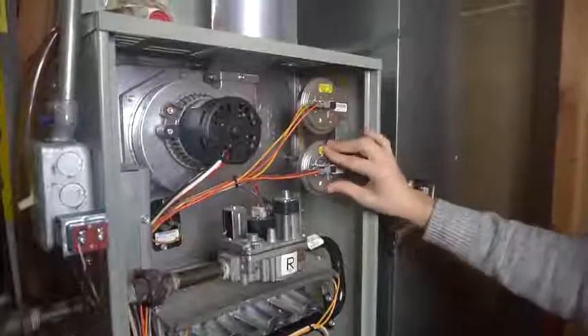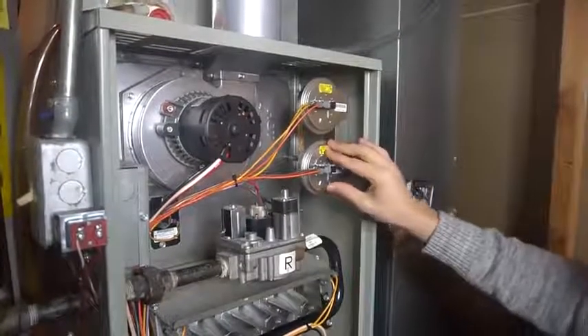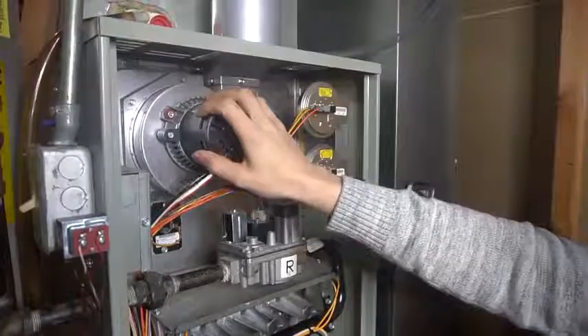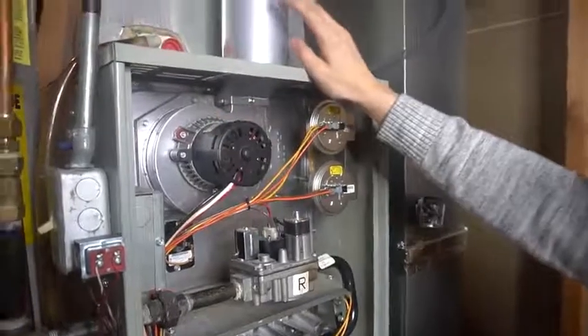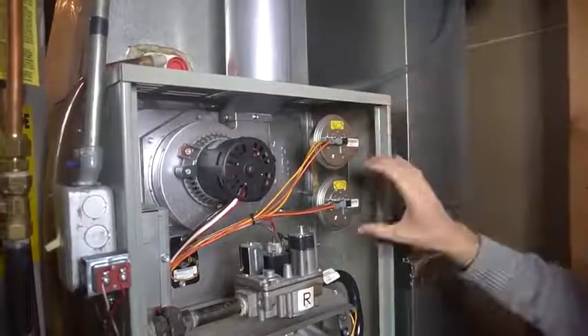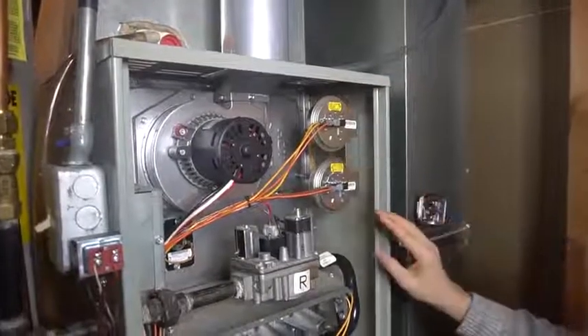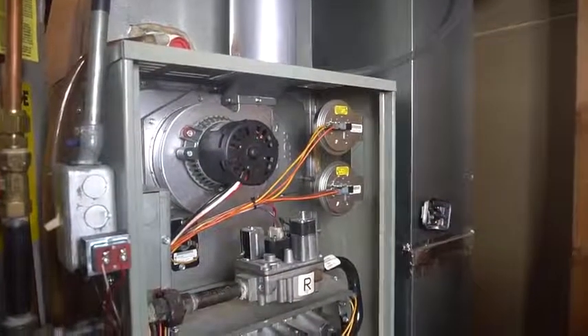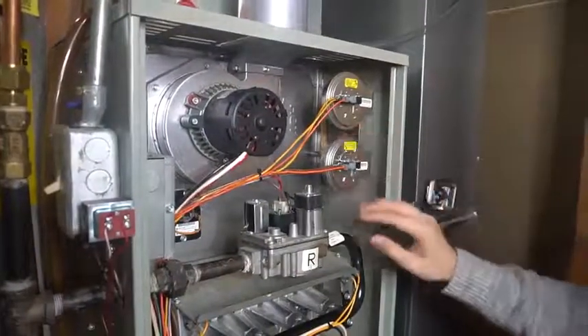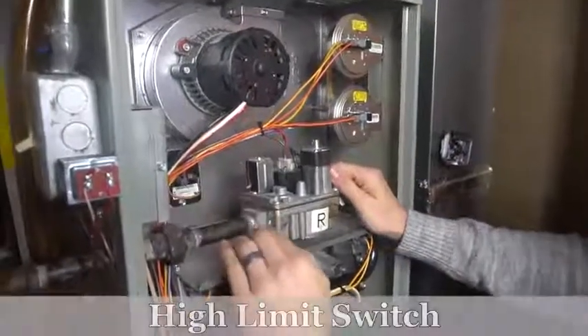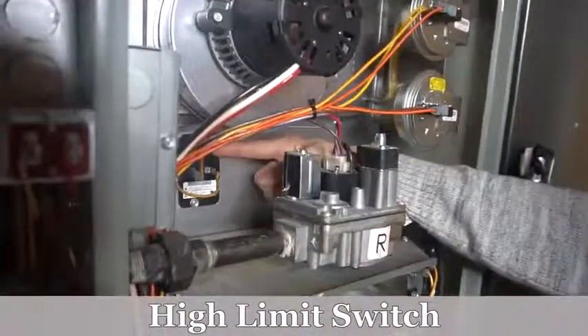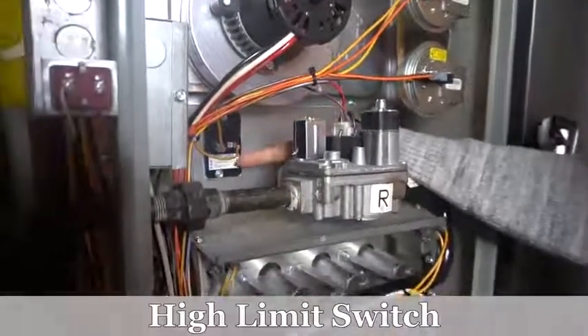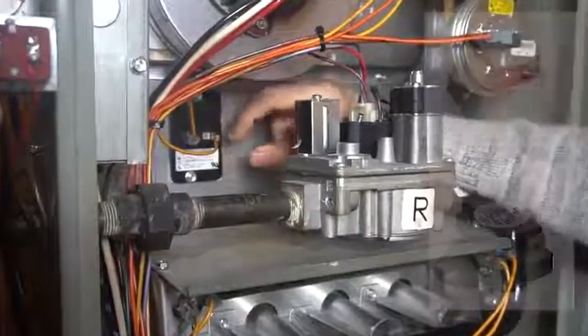So long story short, the pressure switch is a safety that makes sure that your inducer motor is properly exhausting all the combustion gases. If it's not, this safety will trip and turn off the furnace so those gases don't come back into your house somehow. So that's one safety. And another safety right here is the high limit switch. A lot of times it'll be rectangular like this. Sometimes it'll be a small little round circular disc.